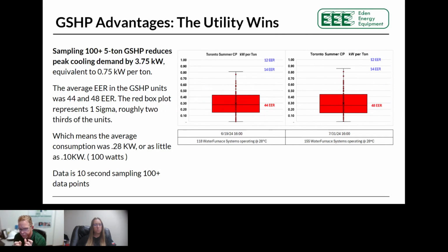You can see that the units were at 44 EER or 48 EER. When you look at the red box, what that represents is a 1 sigma box curve. And so roughly 2/3 of the units were operating at either 44 or 48 EER. This also means when you look at the graph on the left-hand side, you can see that the average kilowatt consumption for this 5-ton unit during a peak cooling load was 0.28 kilowatts and as little as 0.1 kilowatts. So 100 watts for that geo unit to run. Because this data is collected every 10 seconds, it's a really, really good data representation.